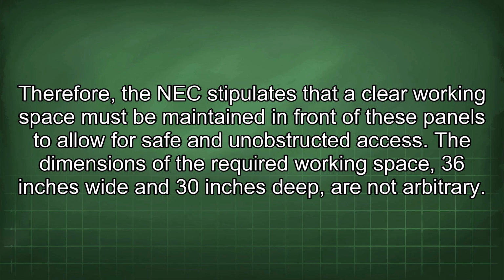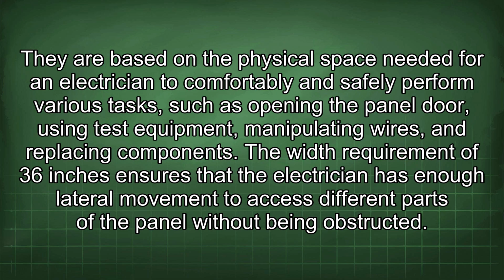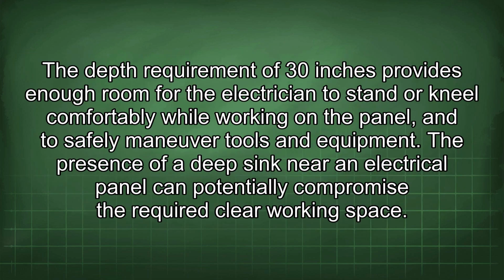safe and unobstructed access. The dimensions of the required working space, 36 inches wide and 30 inches deep, are not arbitrary. They are based on the physical space needed for an electrician to comfortably and safely perform various tasks, such as opening the panel door, using test equipment, manipulating wires, and replacing components. The width requirement of 36 inches ensures that the electrician has enough lateral movement to access different parts of the panel without being obstructed. The depth requirement of 30 inches provides enough room for the electrician to stand or kneel comfortably while working on the panel and to safely maneuver tools and equipment.